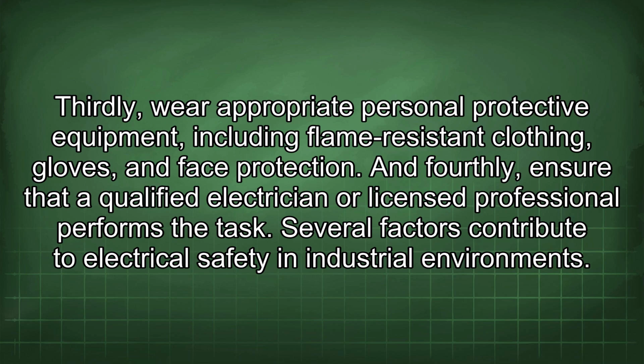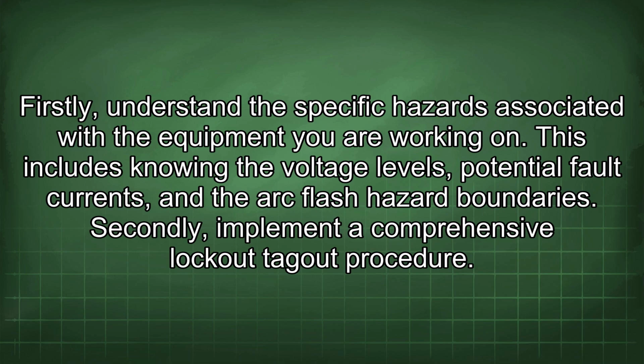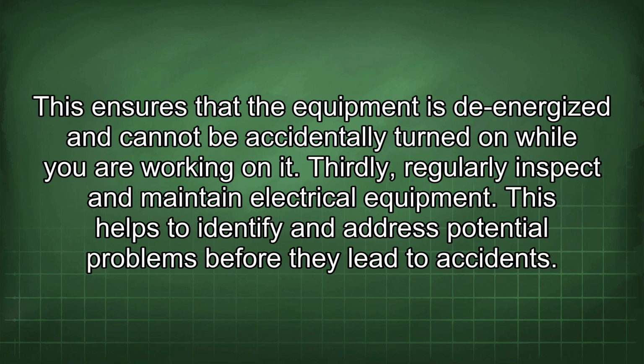Several factors contribute to electrical safety in industrial environments. Firstly, understand the specific hazards associated with the equipment you are working on. This includes knowing the voltage levels, potential fault currents, and the arc flash hazard boundaries. Secondly, implement a comprehensive lockout-tagout procedure. This ensures that the equipment is de-energized and cannot be accidentally turned on while you are working on it.